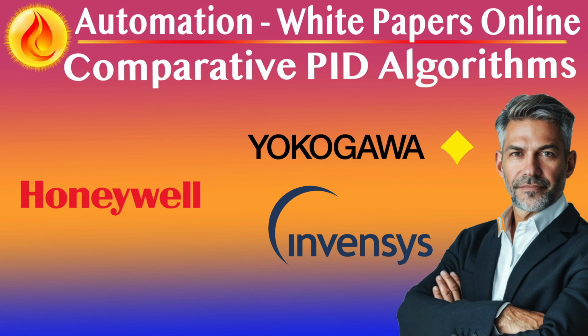Proportional action, gain versus proportional band. Some vendors define proportional action as gain, Kc, while others use proportional band, Pb, which is its reciprocal. Increasing gain makes a loop more responsive but potentially less stable. Decreasing proportional band achieves the same effect as increasing gain.